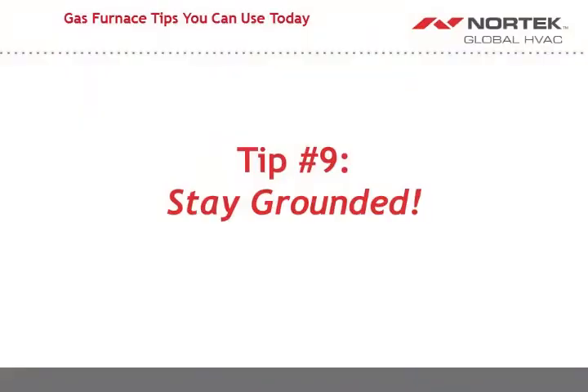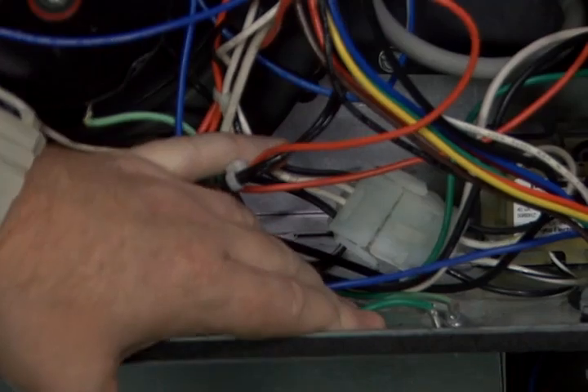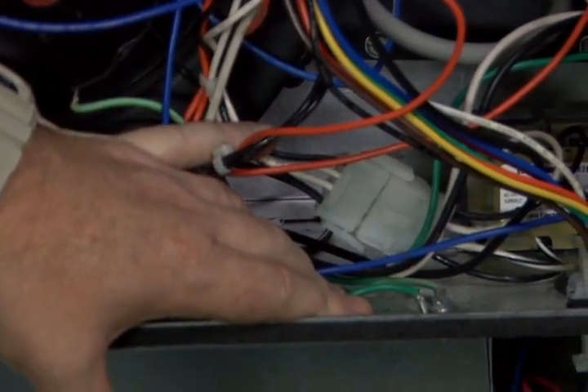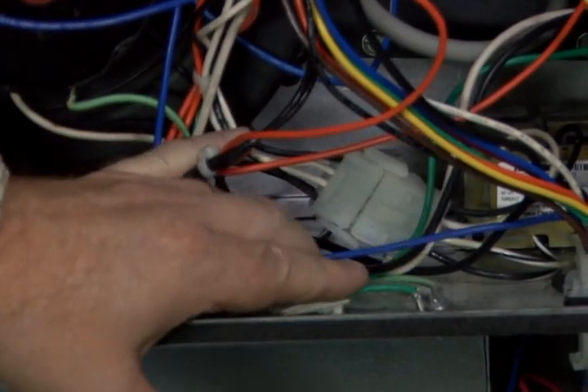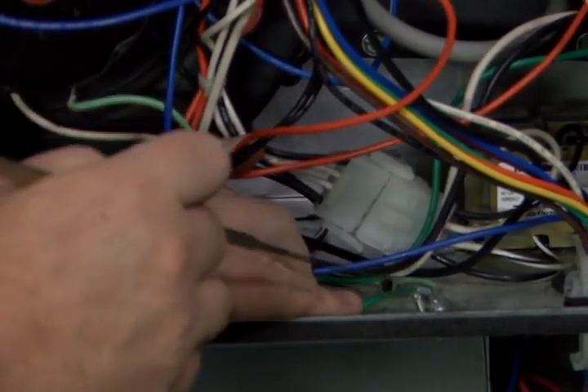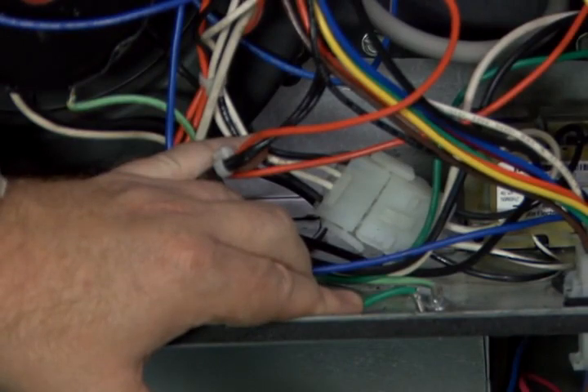Number 9, and that has to deal with the electrical or earth ground reference for the inner electronics, the control boards, and the power circuit that supplies that furnace with power. When we are talking about the earth ground reference of the circuit, we're not necessarily just talking about, do you have that ground wire tight, if you will.